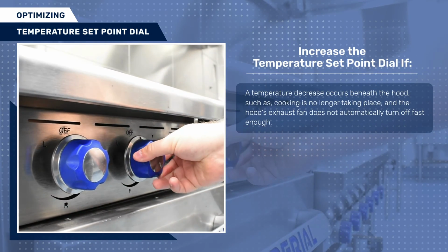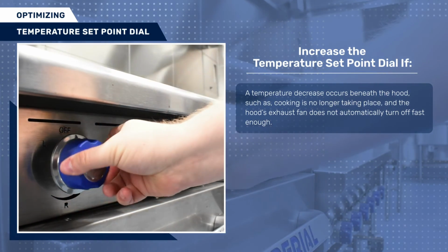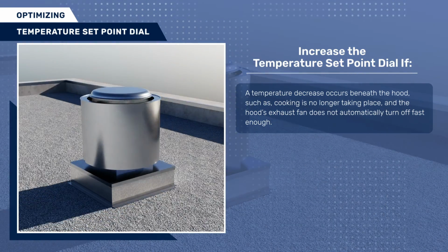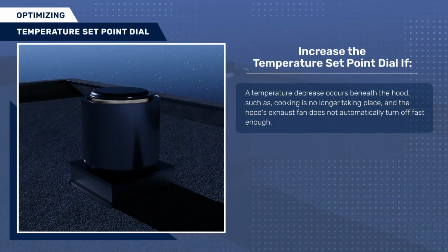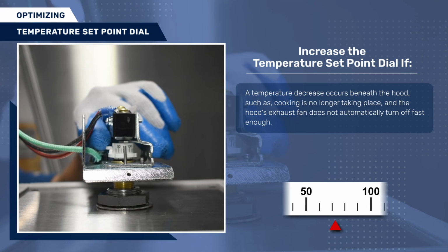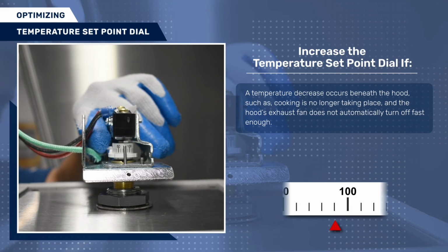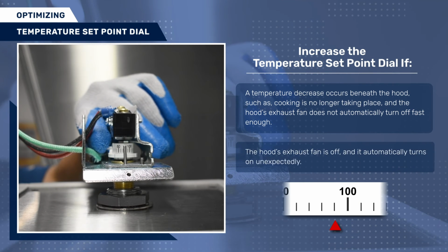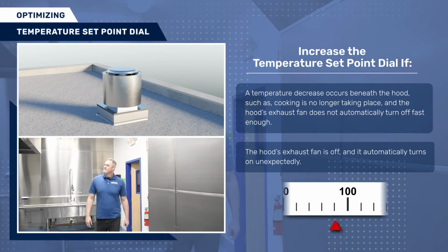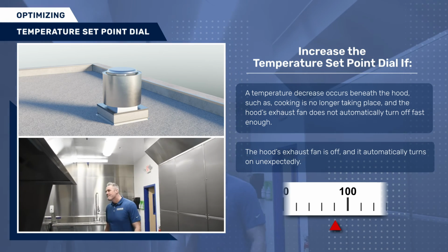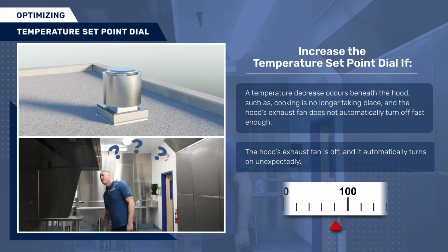In cases where a temperature decrease occurs beneath the hood, such as cooking is no longer taking place, and the hood's exhaust fan does not automatically turn off fast enough, then increase the temperature set point to a level that meets the demand of your kitchen. You may also need to increase the temperature set point if the hood's exhaust fan is off, and it automatically turns on unexpectedly.